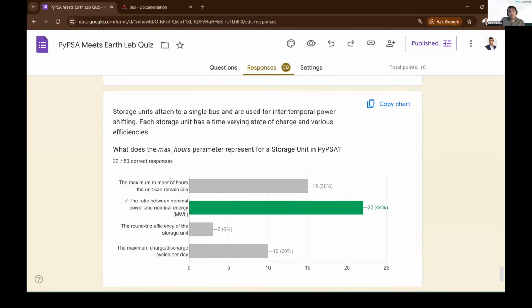The storage unit component is more configured like a typical battery. In a storage unit, you'd define the nominal power - for example, a battery with a nominal power of 100 megawatts. You could then set the max hours parameter - if it's a 400 megawatt hour battery, the max hours would be 4. So max hours is the ratio between the nominal power and the nominal energy the battery can produce.